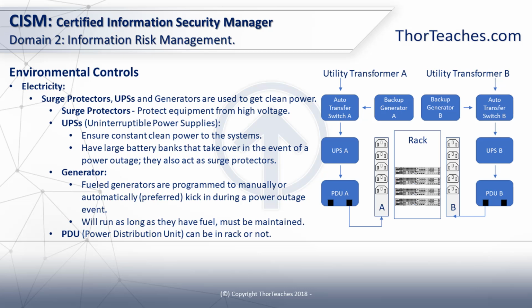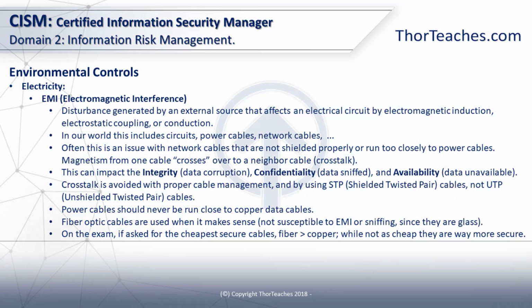Just remember, many data centers only have 20, 30, 40 minutes of backup power on the batteries, so we need to ensure someone can be there and start the generator up if we have it on manual before the battery runs out. And then we talked about the PDU that also protects against the surges, as well as the distribution of the power, and those could be racked or not. One of the other things we need to be aware of with electricity, and which can cause us problems other than the power outages or fluctuations, is EMI, electromagnetic interference.